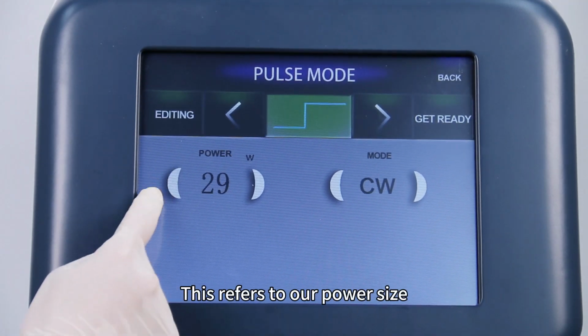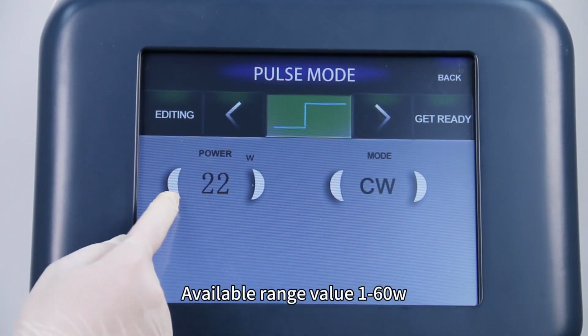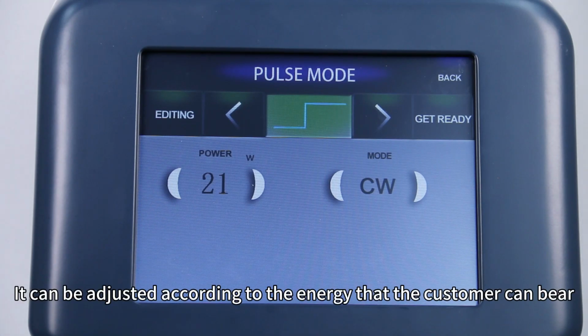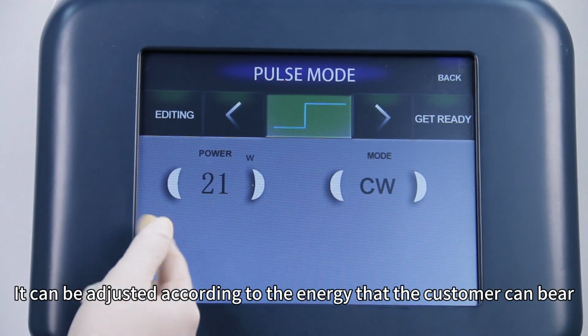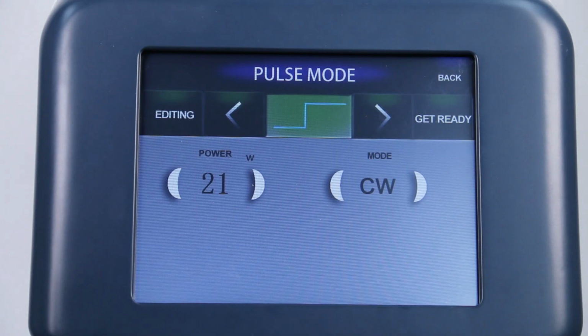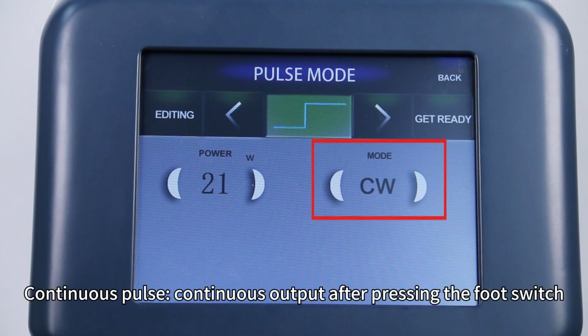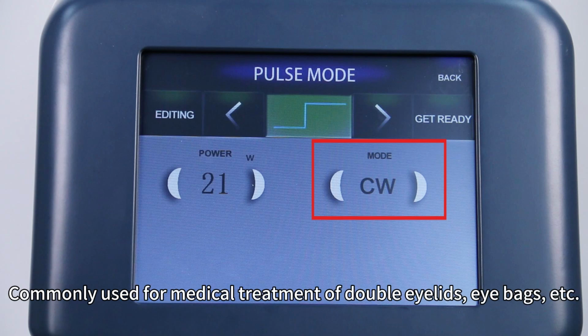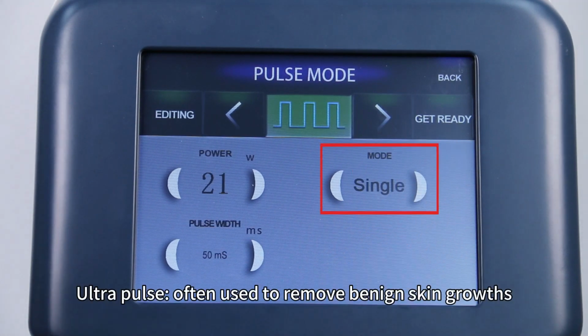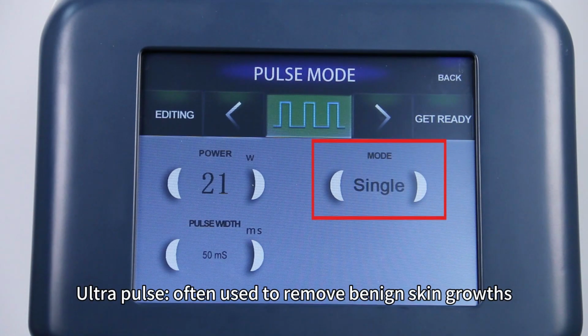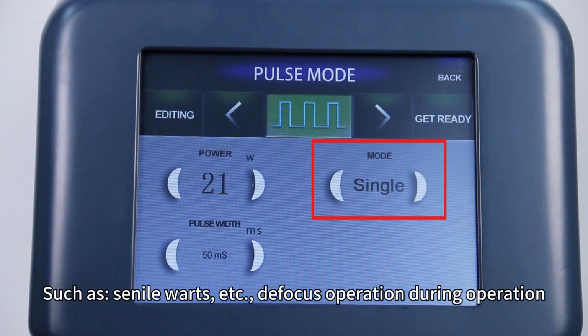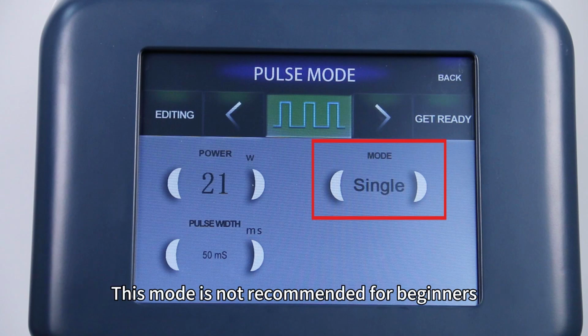This refers to the overall power size. Available range 1 to 60 watts. It can be adjusted according to the energy that the customer can bear. Continuous pulse: continuous output after pressing the foot switch, commonly used for medical treatment of double eyelids, eye bags, etc. Ultra pulse is often used to remove benign skin growths, such as senile warts. It is difficult to operate, so this mode is not recommended for beginners.